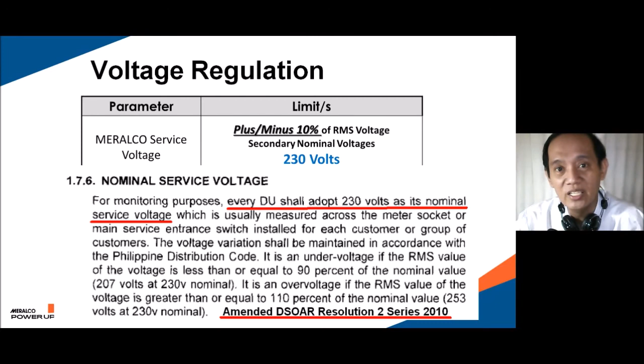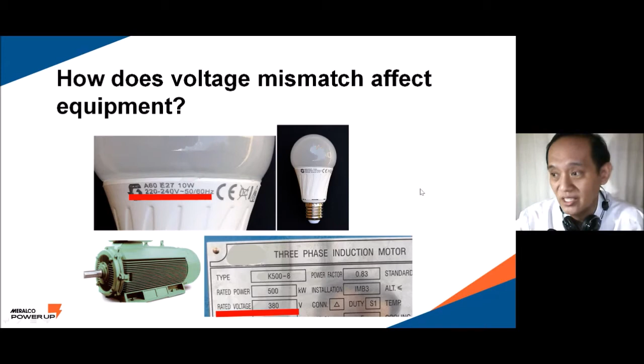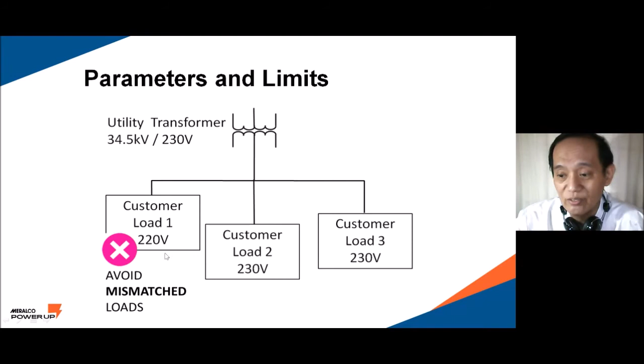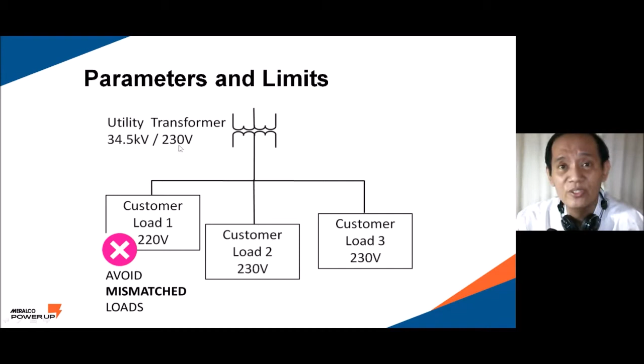So voltage mismatch happens when you have equipment that does not match the supply given by the distribution utility. In this case, the induction motor is rated at 380 volts and the standard is 400 volts. You are going to have serious voltage mismatches. In this example, SM is basically most of the time primary metered, so you supply the transformer. So when your tenant is having a 220 volt load and the other tenants have 230 volts, that tenant will always have problems regarding the operation of the equipment because of the mismatched loads at 220 and your supply of 230 volts.